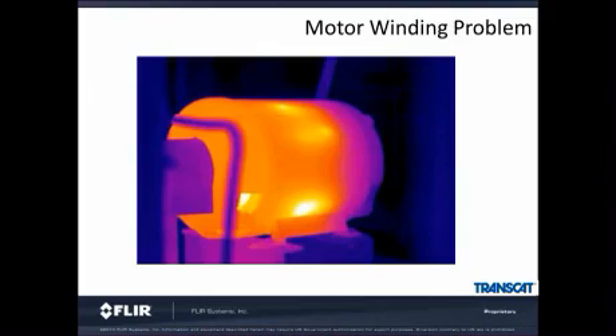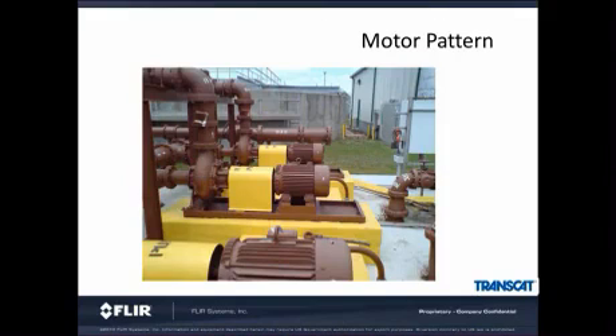Here's a thermal picture of a motor with a distinguishable temperature mark from problems in the windings. In fact, there are three distinct marks. The arrow's pointing to the one at the top, there's one slightly to the right, and then there's one directly below it. Since these spots are small, a spot gun would have trouble finding them. As we have discussed earlier, spot guns have very small spot size ratios. Finding a winding problem in a motor is near impossible. And as we know, every industrial factory has many, many motors. Keeping them running is very important, and a thermal camera will make that much easier.